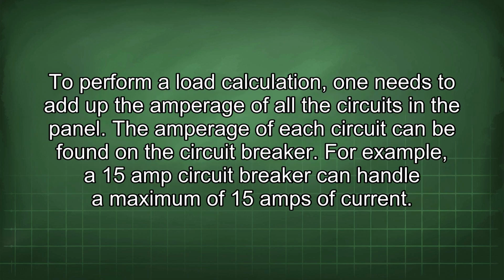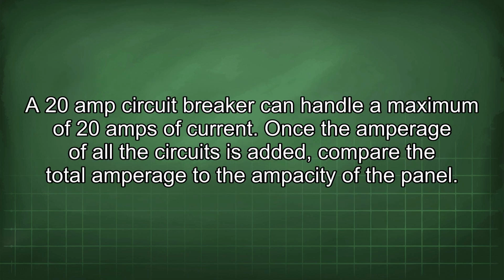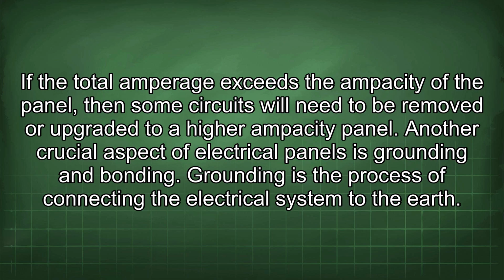To perform a load calculation, one needs to add up the amperage of all the circuits in the panel. The amperage of each circuit can be found on the circuit breaker. For example, a 15 amp circuit breaker can handle a maximum of 15 amps of current. A 20 amp circuit breaker can handle a maximum of 20 amps of current. Once the amperage of all the circuits is added, compare the total amperage to the ampacity of the panel. If the total amperage exceeds the ampacity of the panel, then some circuits will need to be removed or upgraded to a higher ampacity panel.